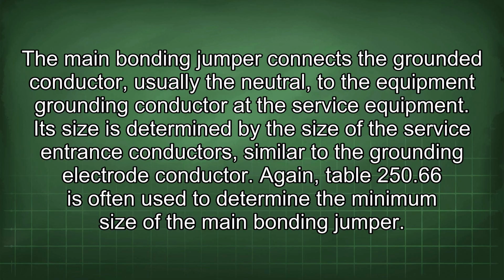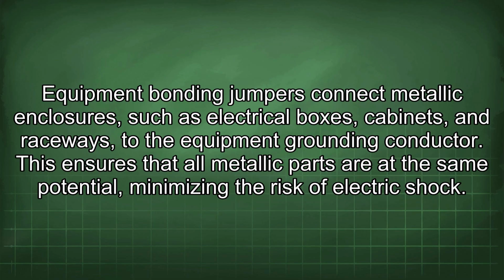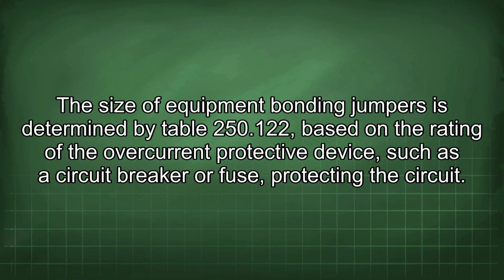Again, Table 250.66 is often used to determine the minimum size of the main bonding jumper. Equipment bonding jumpers connect metallic enclosures, such as electrical boxes, cabinets, and raceways, to the equipment grounding conductor. This ensures that all metallic parts are at the same potential, minimizing the risk of electric shock. The size of equipment bonding jumpers is determined by Table 250.122 based on the rating of the overcurrent protective device, such as the circuit breaker or fuse, protecting the circuit.